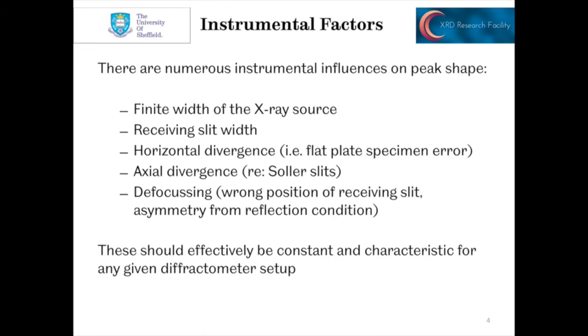So we've looked at instrumental setups before. There are various instrumental influences on the peak shape: the width of the x-ray source, the size of it, the optics that you have in the machine, the receiving slit width in particular right in front of the detector. That's going to have a big impact on the resolution of the diffractometer.